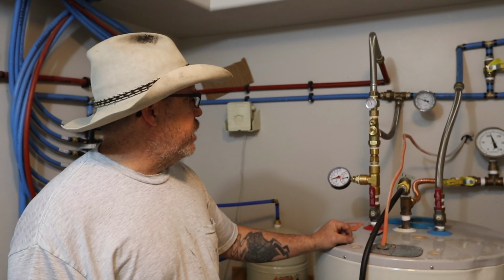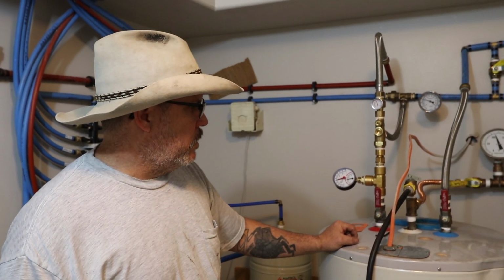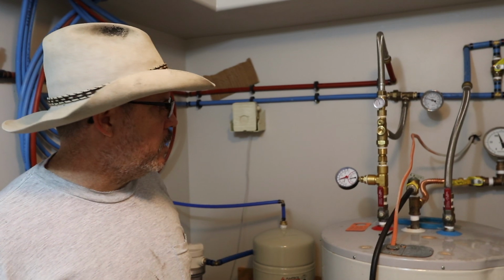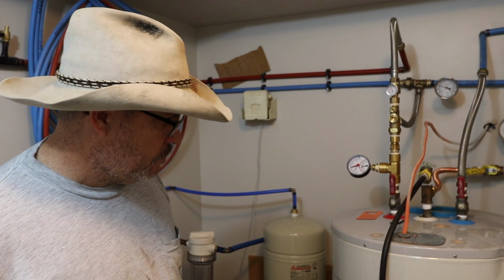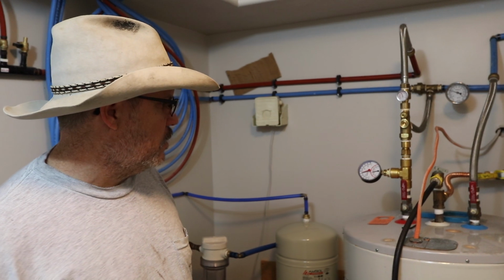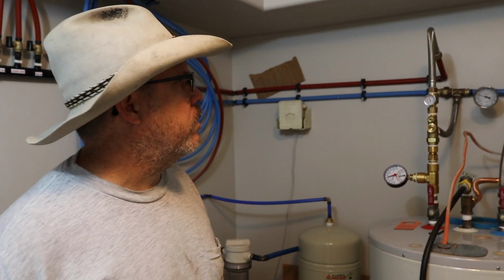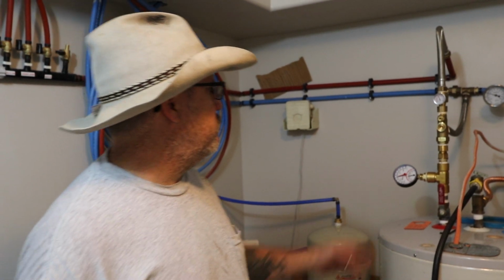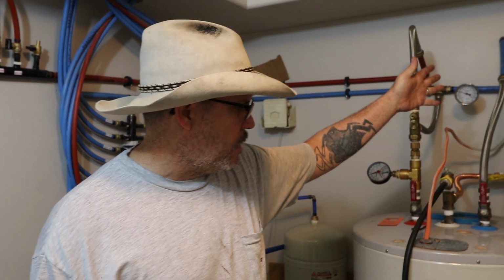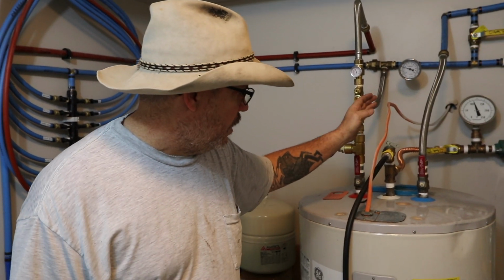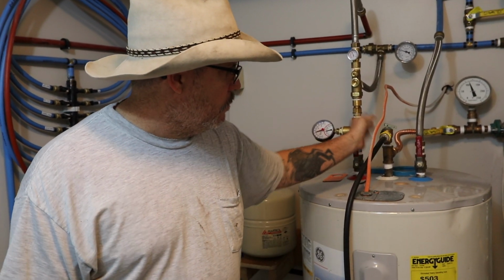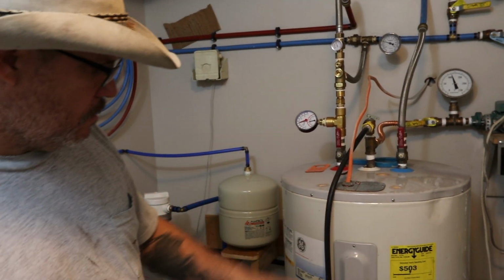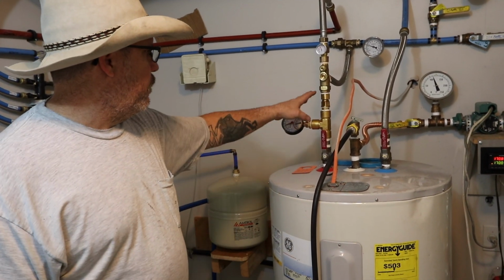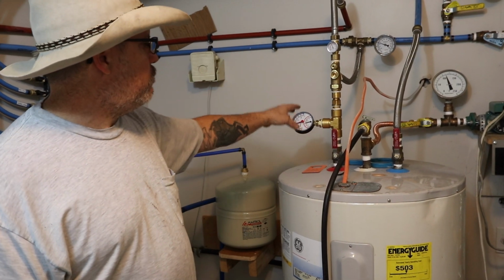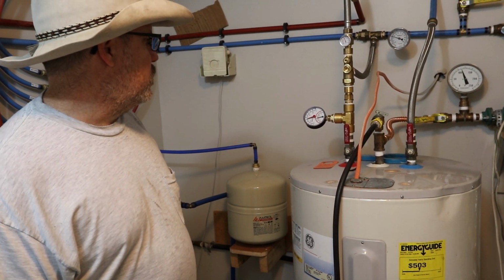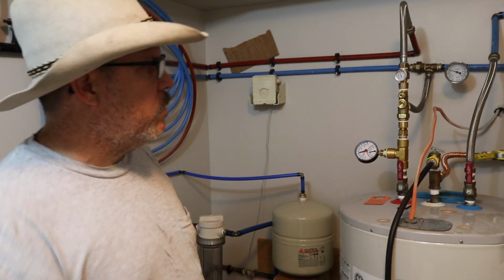And yeah, I've got babies, so I don't want to scald my babies, but I don't want to run out of hot water either. This is 50 gallons and it maintains hot water. I can take as long a shower as I want, depending on how big a water bill I want to have. So I preheat my cold water. If I need a booster, then I'll turn that pump on through a thermostat. It'll help maintain the heat, and then I bring that temperature back down before I go out to my faucets. So that's my domestic water heating system.